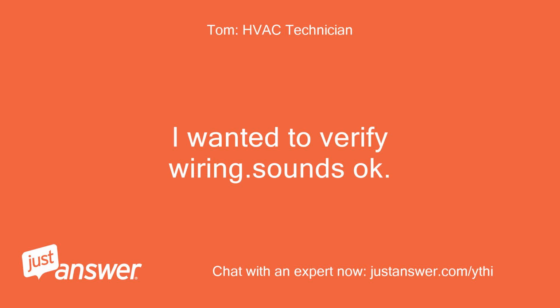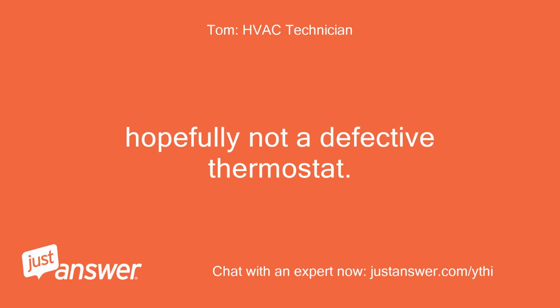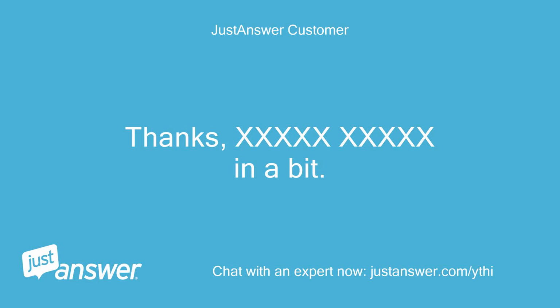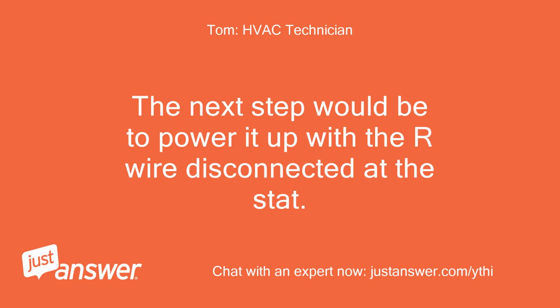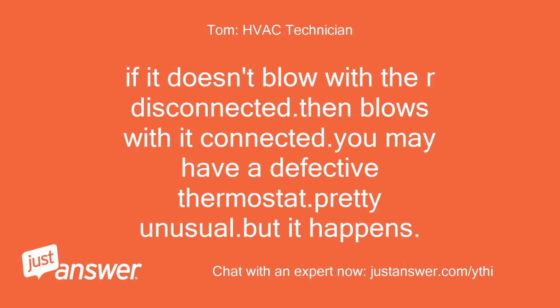I wanted to verify wiring. Sounds okay. Hopefully not a defective thermostat. Thanks, in a bit. The next step would be to power it up with the R wire disconnected at the stat. If it doesn't blow with the R disconnected, then blows with it connected, you may have a defective thermostat. Pretty unusual, but it happens.